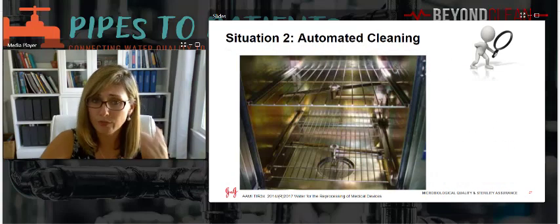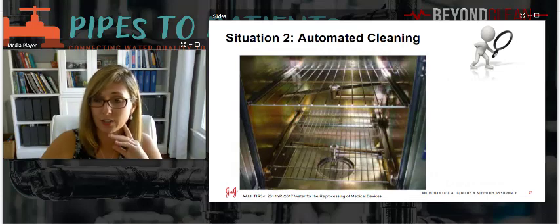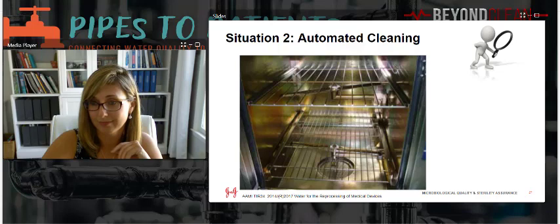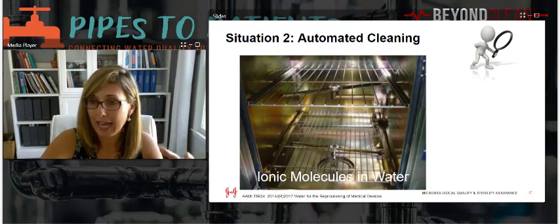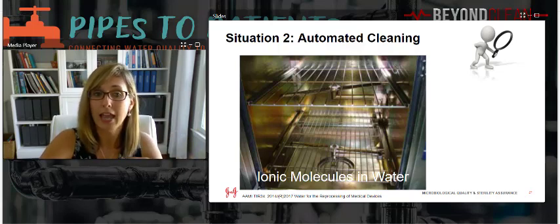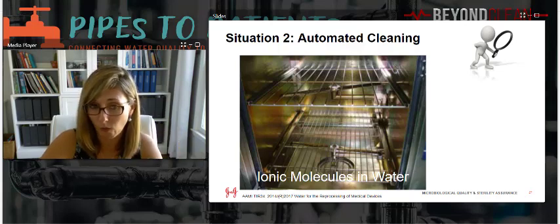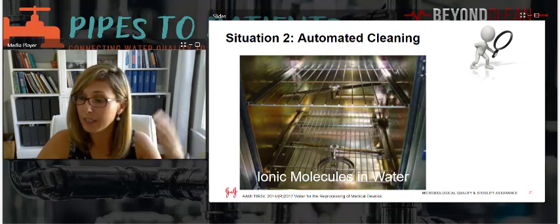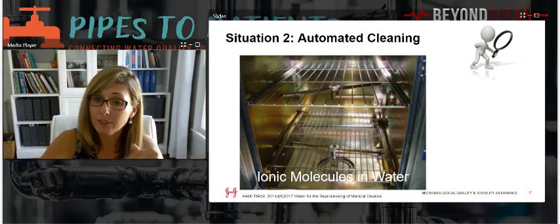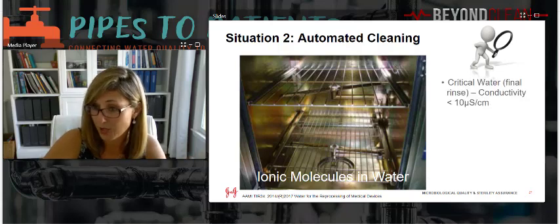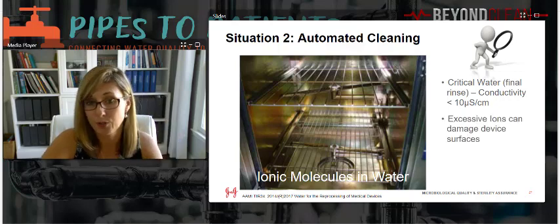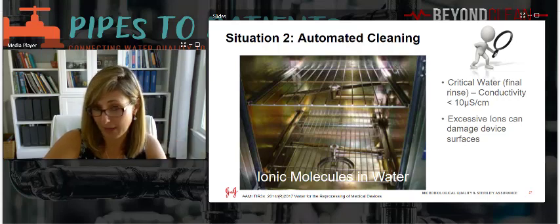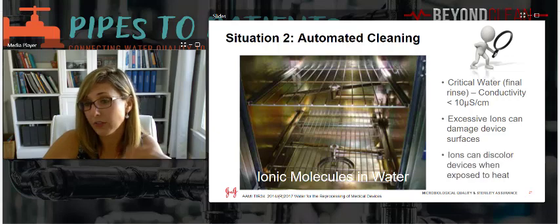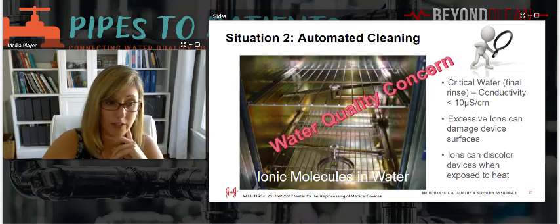So let's look at another one. If you put them in the washer disinfector and your washer disinfector looks like this, a beautiful iridescent color, is this a problem? Yep. So this again goes back to what you might have as far as ionic molecules remaining in your water. When you consider the final rinse of the water, which is supposed to be critical, you shouldn't have these remaining ionic molecules left in, because they should have been rinsed out during that process. But if these ionic molecules, measured through conductivity, have the opportunity to be heated, we know that they can damage and discolor during the process. So we'll see not only this discoloration on our washer disinfector, but also on the devices coming out. So it is a water quality concern.